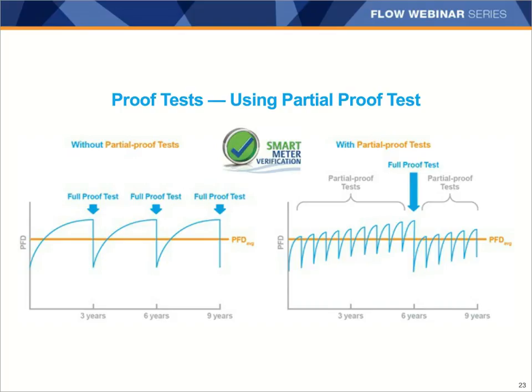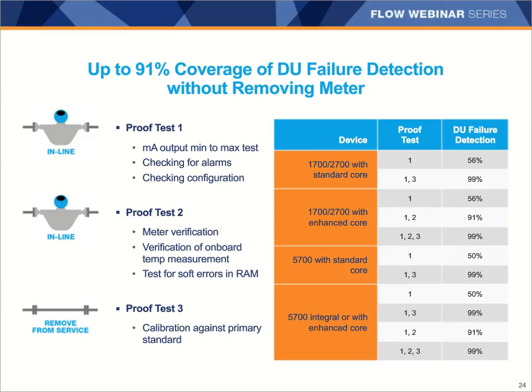So you guys might be familiar with this when you think about partial valve stroking. I think that's probably the most common example. But basically, as you see in the graph on the right, even though the partial proof tests don't bring the equipment back to the original PFD number, it drops it enough to extend the interval of the required full proof test and still maintain the same average PFD. So the Micro Motion model 1700, 2700, and 5700 all take advantage of the smart meter verification diagnostic in helping with partial proof testing and extending the full proof test intervals or full calibration.